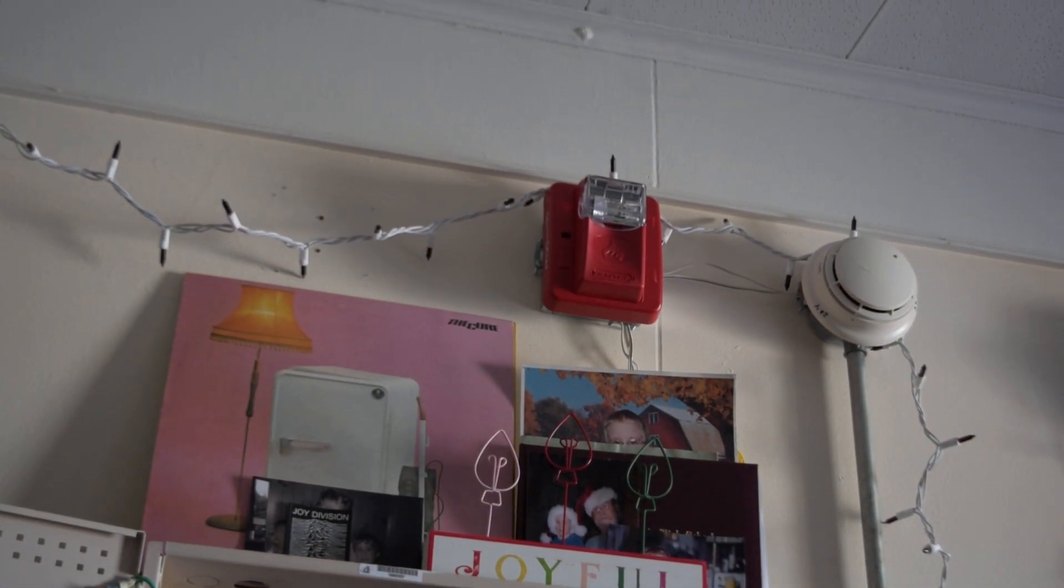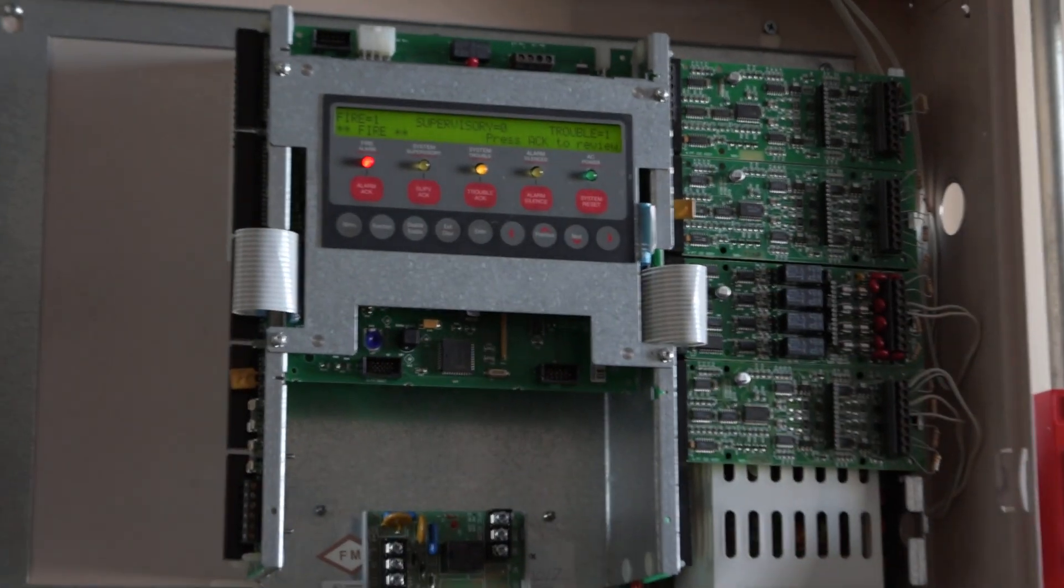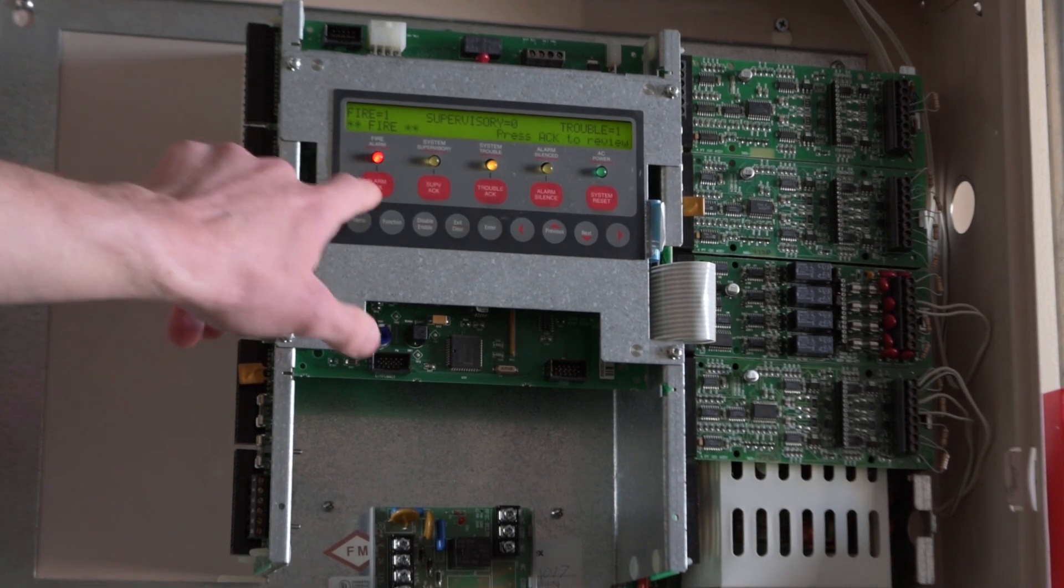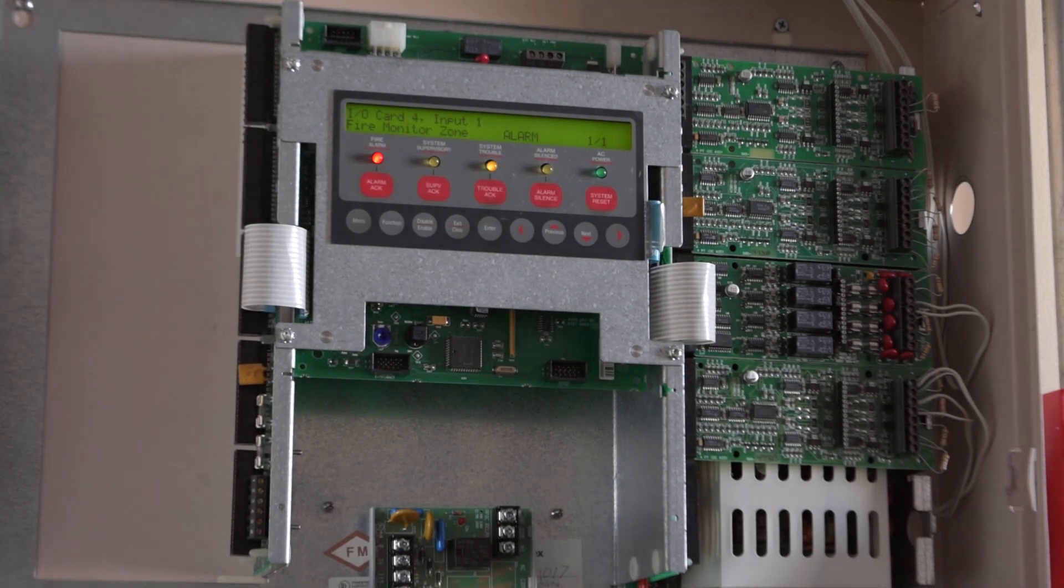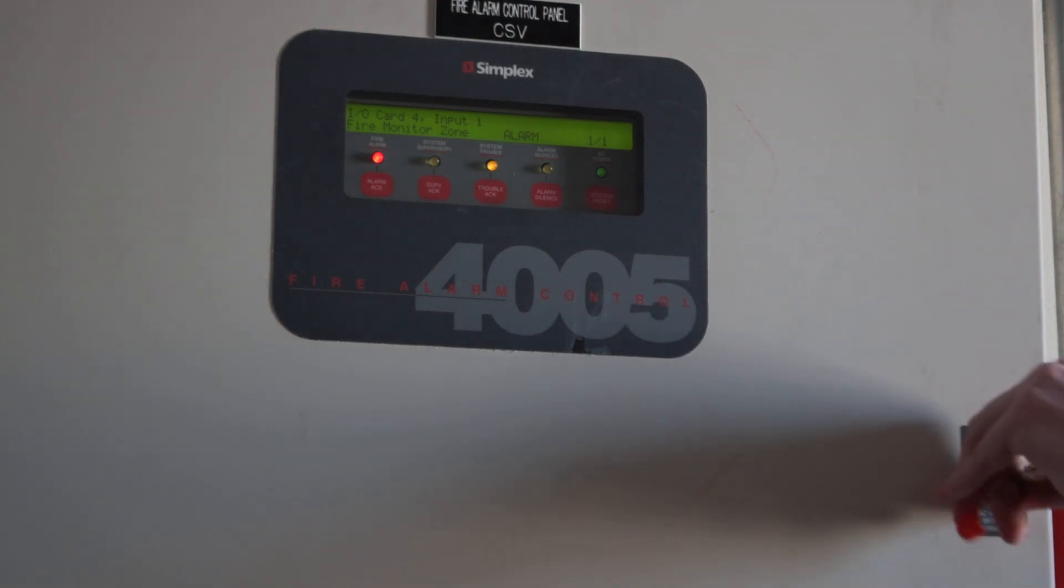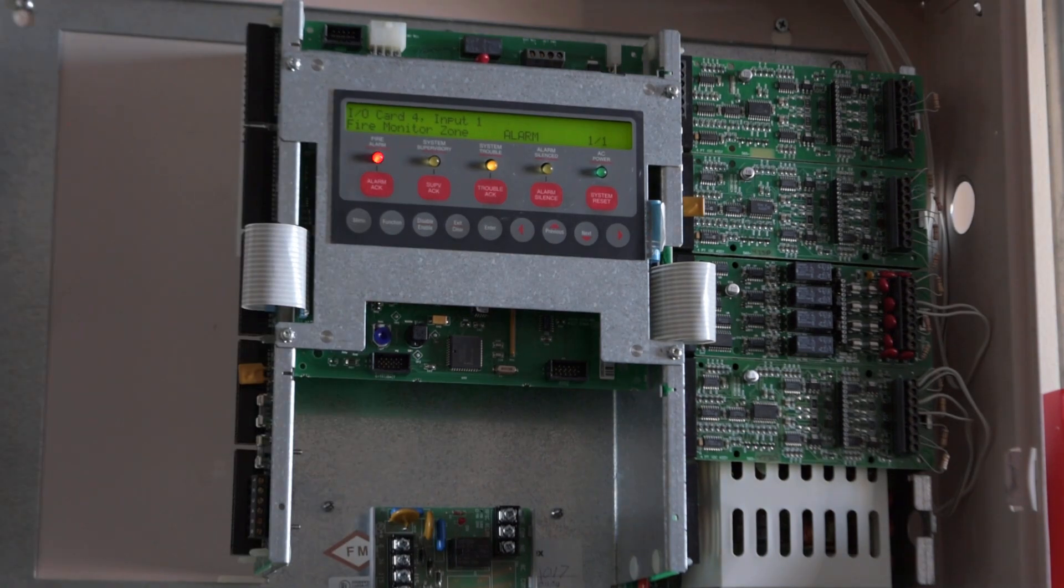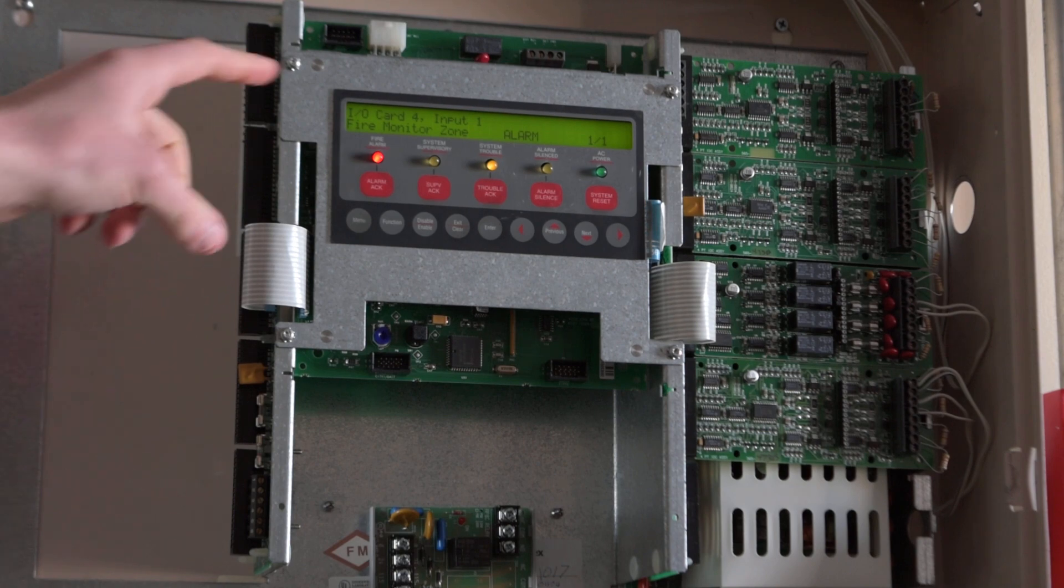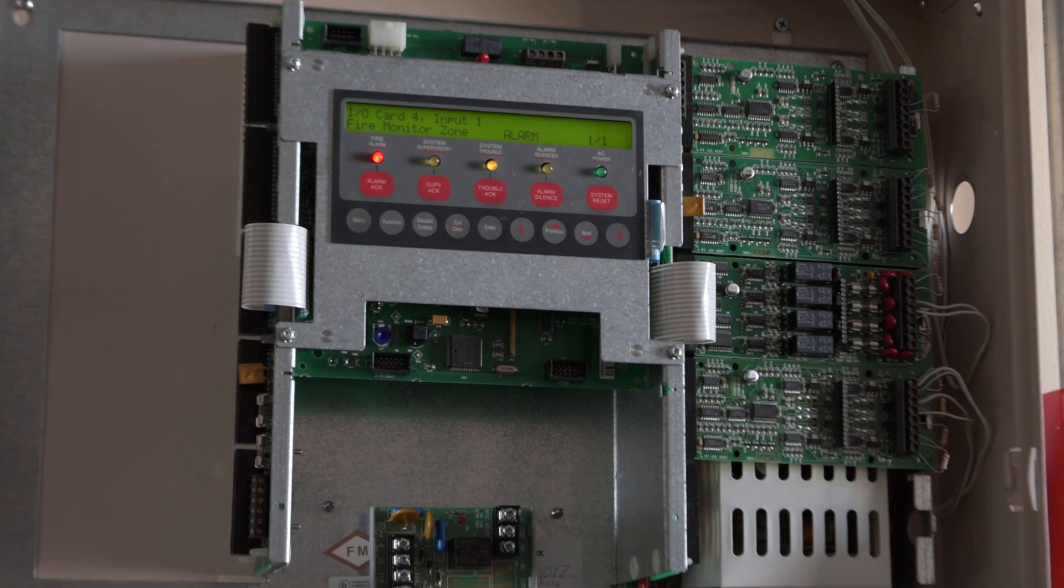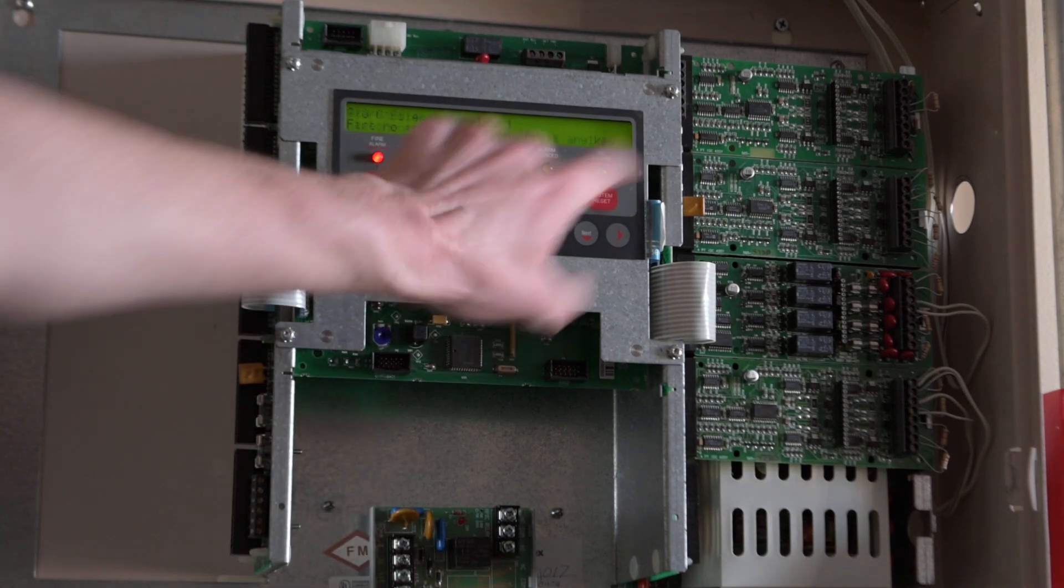Three, two, one. There we go, we have an alarm. And if we look at our signal it is flashing. We'll get in nice and close and we'll go ahead and acknowledge that. And let me grab my keys and we will reset the pull station. And I must have tripped it again because that happens sometimes. These panels do have zone re-alarm. As you can see, I/O card input one fire monitor zone alarm one out of one. I did not do any custom labeling yet to label the zones, but that can be done of course. So we'll go ahead and hit alarm silence.